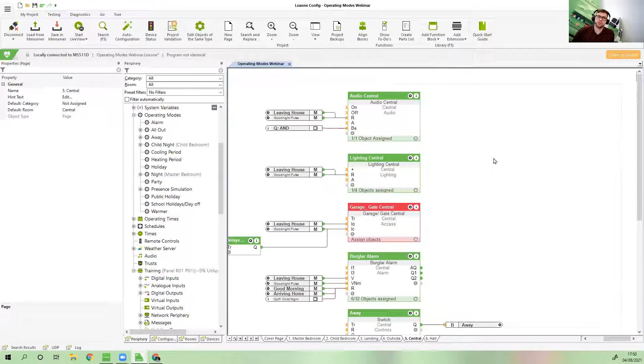The reason the daylight responsive lighting block is not the correct block to use is because that's designed for hitting a certain lux level inside the room, rather than what the external lux is doing. But it's irrespective of the moods you set, so it's always going to be overriding your moods. The daylight responsive lighting controller is designed for offices. It has a specific function.